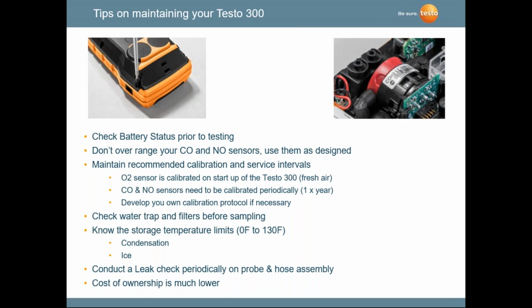Storage limits: be careful, especially in northern Canada, about keeping these inside a vehicle overnight. The big thing is the condensation. You go from a very cold environment to a warm boiler room. You could create some condensation internally in the instrument, so be careful with that. And certainly if you forget to dump out the water in a water trap and you keep it overnight and it freezes, ice expands and could crack the water trap. And then, as I indicated, conduct leak checks periodically.